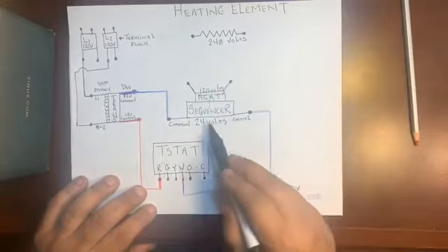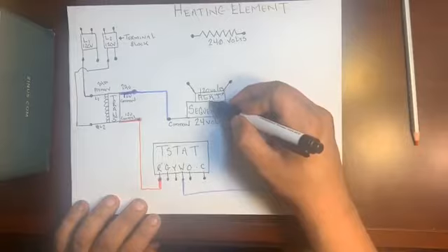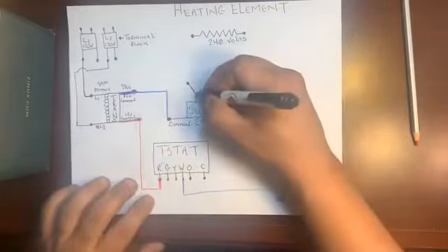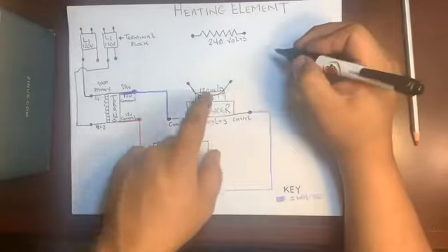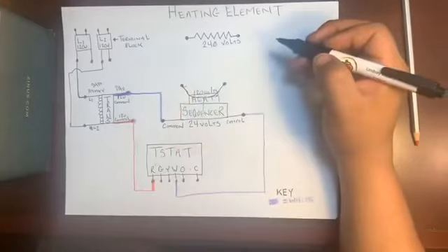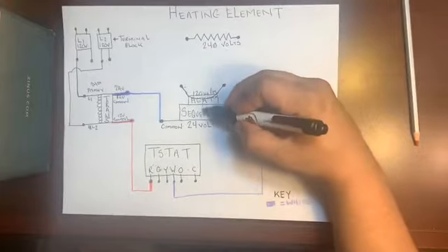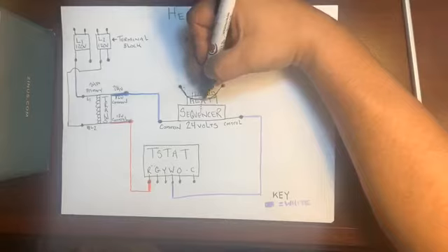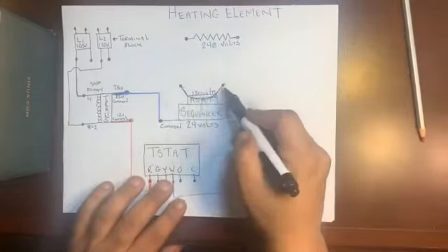So when you get 24 volts across the bottom of the heat sequencer, this T will slowly rise up through the both stages, and then when it does, it activates and it closes this circuit right here. Because normally power can get in through here, but it cannot exit through here until there's 24 volts to the bottom of the heat sequencer, and then the bimetal will float up, and then the circuit will continue and close, and then power can travel through.